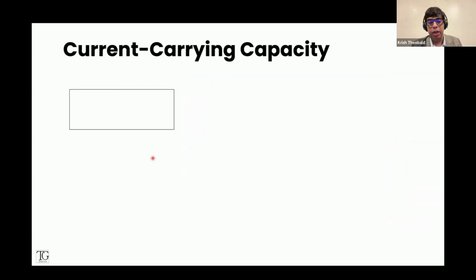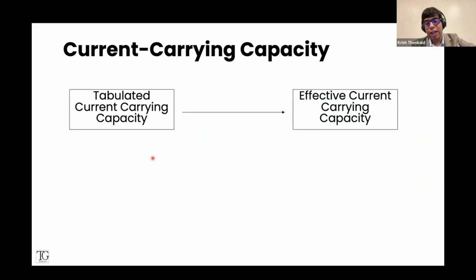So we have to select our assemblies accordingly as well. Current carrying capacity. Now we have your tabulated values, where the manufacturer says 2.5 square mm can carry 20 amps, for instance. However, these values are very rarely what the installation will actually use, because we have to correct to our effective current carrying capacities. Most importantly, we have the factor of grouping. So how many cables are grouped together? I often hear that in a single 25 millimeter conduit, we have something like 6 circuits, which is entirely ridiculous. Not only because it breaks the cardinal rule of only occupying 35% of the conduit's internal cross-sectional area, but because we're now greatly affecting the cable's heat dissipation.